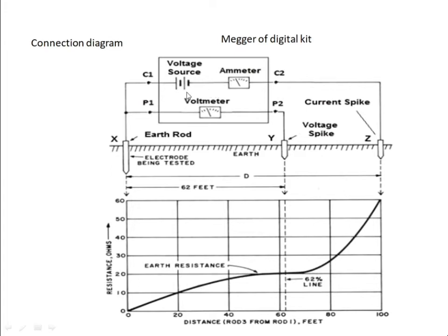The readings are tabulated. You see the resistance graph, how resistance varies according to the distance. Initially, the resistance increases slowly, linearly. When it reaches 62% of the distance, it becomes a flat curve, that is, the resistance is constant. After crossing that point, the resistance will increase drastically.